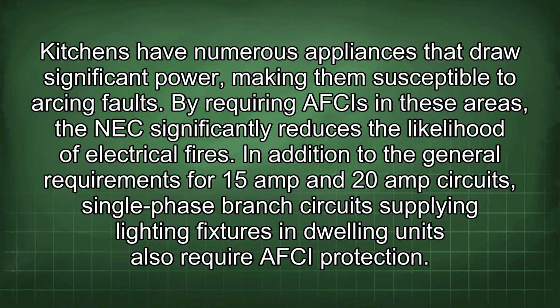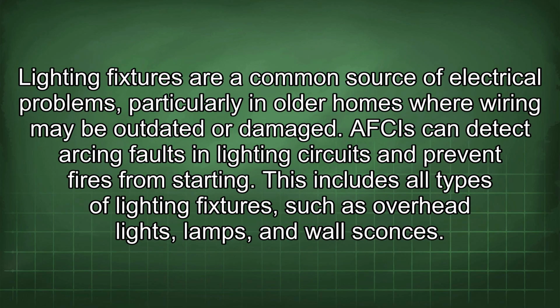In addition to the general requirements for 15 amp and 20 amp circuits, single-phase branch circuits supplying lighting fixtures in dwelling units also require AFCI protection. Lighting fixtures are a common source of electrical problems, particularly in older homes where wiring may be outdated or damaged. AFCIs can detect arcing faults in lighting circuits and prevent fires from starting. This includes all types of lighting fixtures, such as overhead lights, lamps, and wall sconces.